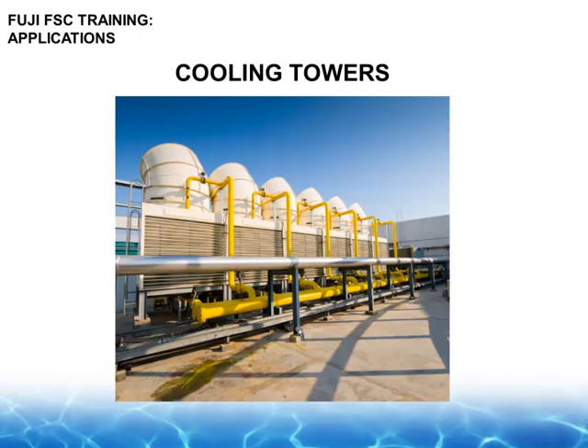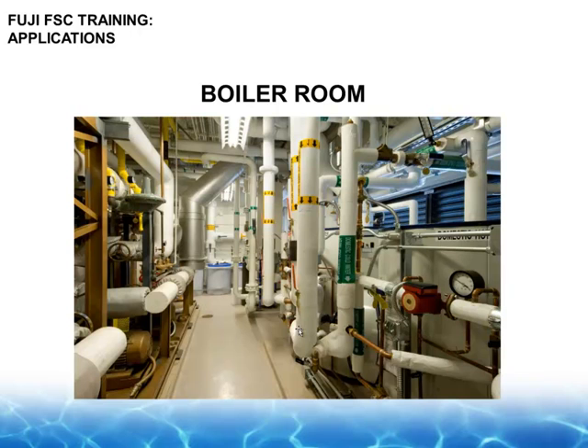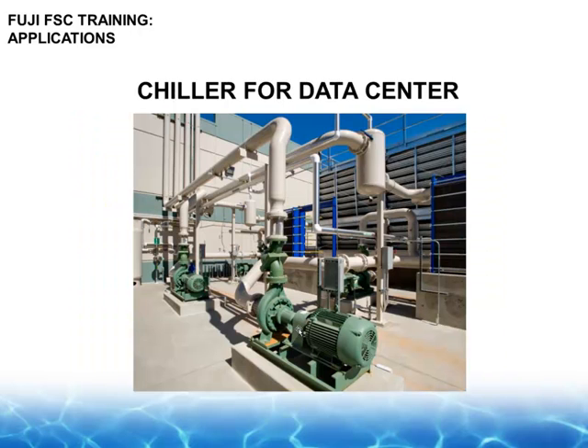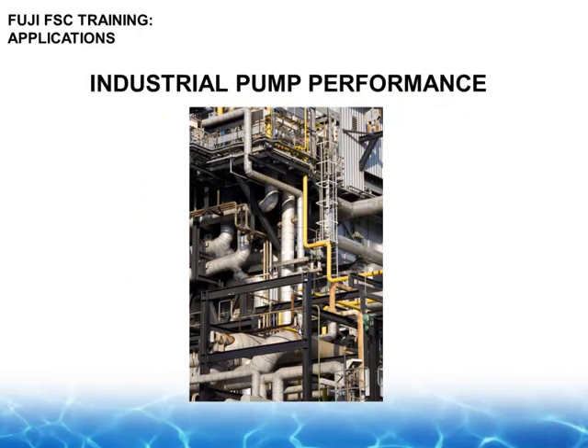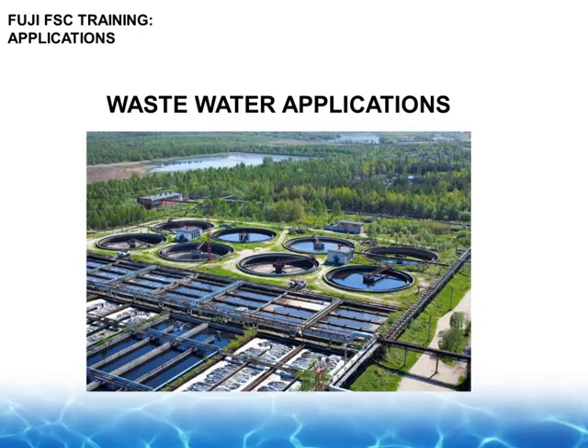You can go on the roof with a cooling tower application. You can go in the basement to look at your boiler room. You can go look at a data center. You can go look at any industrial wastewater application. Basically what you're monitoring is pump performance, and you may require some effort to get to those flows. You may have to remove insulation. You may require scaffolding there. But again, it's all about the pump performance, and that's the value of using this portable technology.